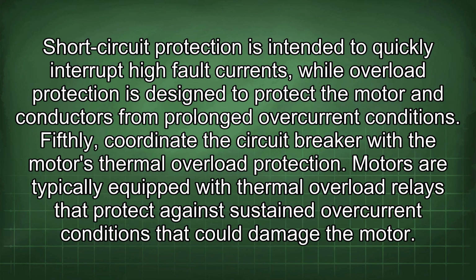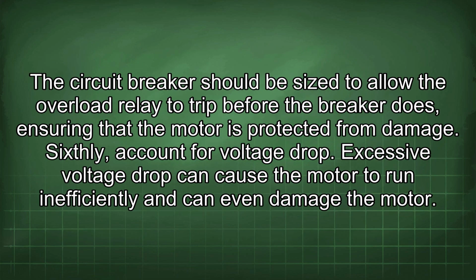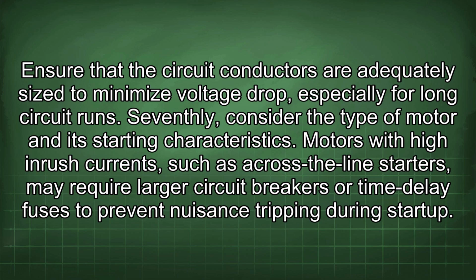Fifthly, coordinate the circuit breaker with the motor's thermal overload protection. Motors are typically equipped with thermal overload relays that protect against sustained overcurrent conditions that could damage the motor. The circuit breaker should be sized to allow the overload relay to trip before the breaker does, ensuring that the motor is protected from damage. Sixthly, account for voltage drop. Excessive voltage drop can cause the motor to run inefficiently and can even damage the motor. Ensure that the circuit conductors are adequately sized to minimize voltage drop, especially for long circuit runs.